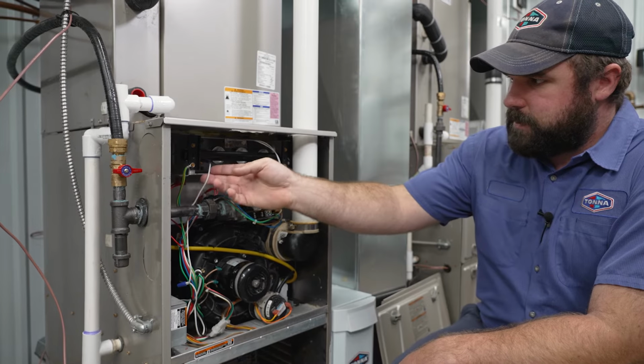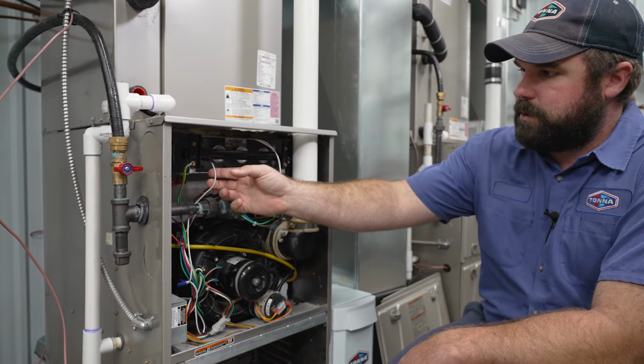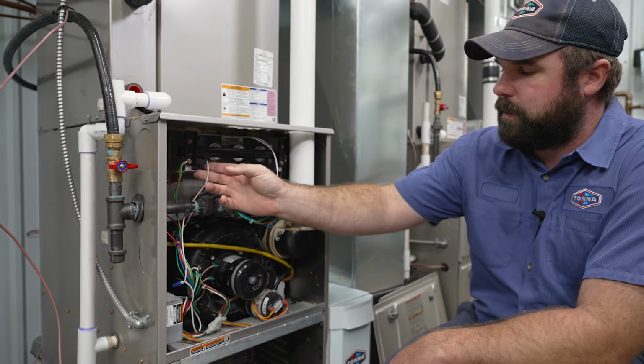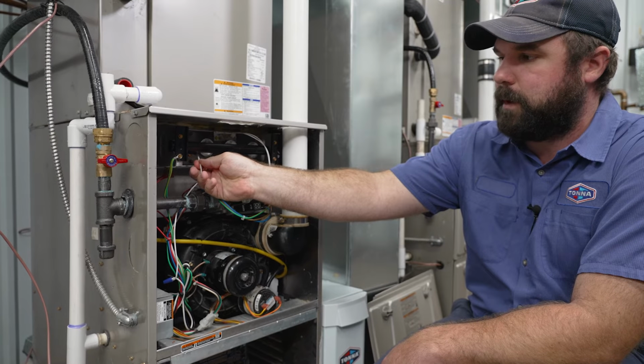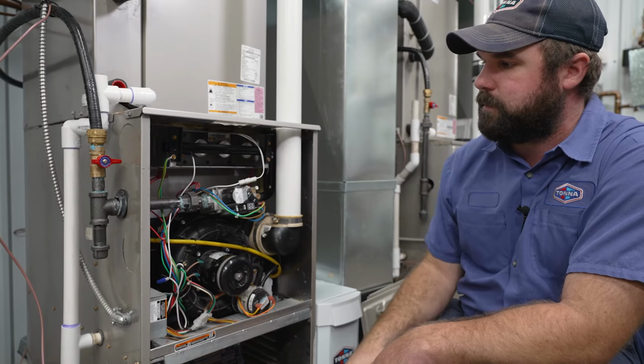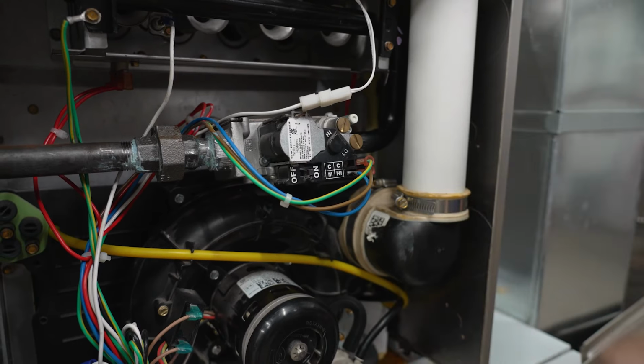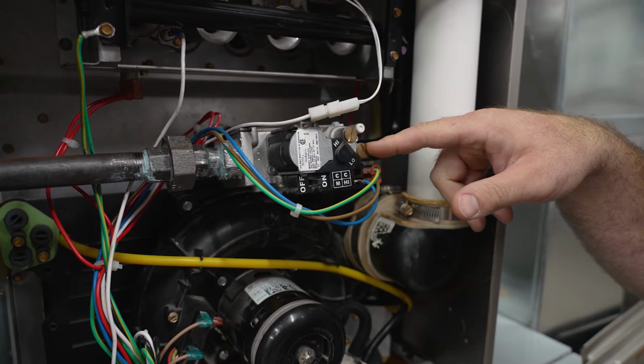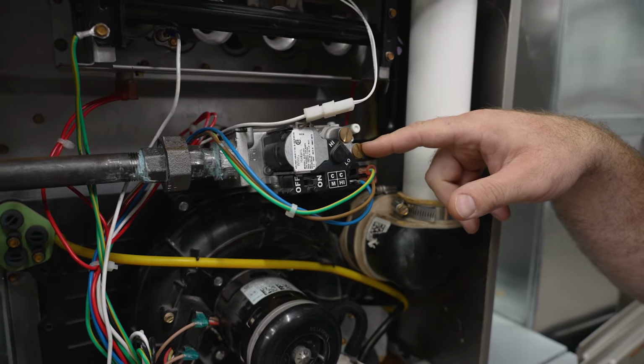Your igniter will glow bright red in most new furnaces and will ignite the flame. And then you have your flame sensor here. We'll check that during operation. We'll hook our meter into that and check it in microamps DC to make sure it's reading within spec as well. This is your gas valve. The operation of that will be checked when the system is up and running.